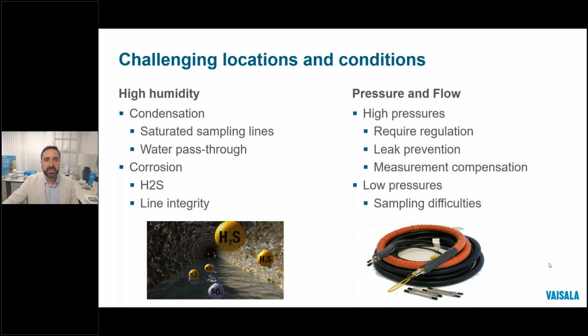Drying also means that these instruments are reporting gas values on a dry basis rather than a wet basis. And what that means simply is that when you remove the water vapor from the sample stream, the remaining gas concentrations are going to appear higher as the water vapor that was in the gas phase was removed. So unaccounted for, this is going to skew the measurements a little higher, making it seem like there's more methane in that part of the process than there actually is. Correction factors are often applied to account for this, but without actual accurate measurement, it's really just an educated guess. Next, please.